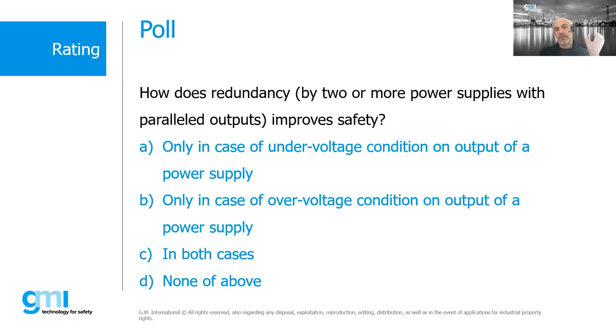Of course, there is the overvoltage protection side. About the undervoltage condition, it's true that redundancy improves safety in the sense that it reduces the probability that this condition could happen.